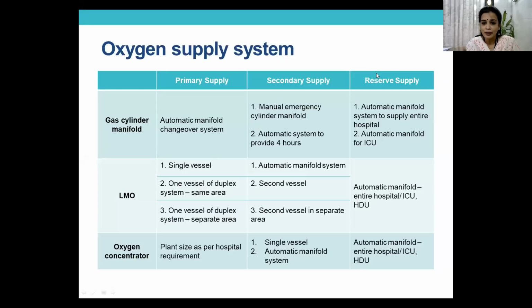What is the secondary supply? Near to your existing system, you need to have a manual emergency cylinder manifold, which should take care in case there is a small problem in your primary manifold. This system should provide supply for at least 4 hours. That's your secondary supply. Then you also need to have a reserve supply, which should be elsewhere. It need not be as large as the primary supply, but it should be in a location away from the primary location. So you should have it in another building, or probably in the same building in another location, with a separate connection. Now, if you're having ICUs, you can ignore the first part and just have only your ICUs connected as a reserve supply, because that is your critical load.